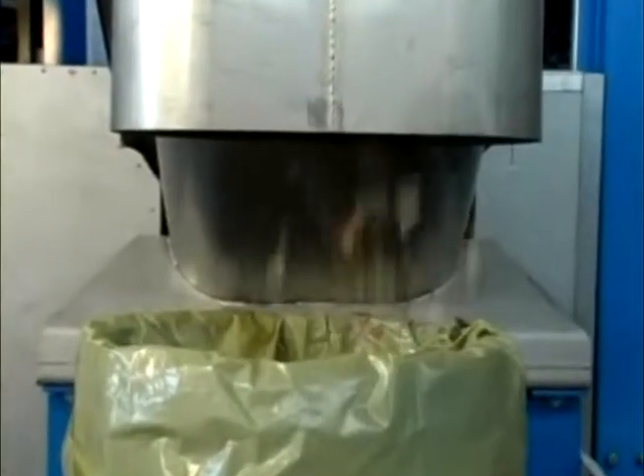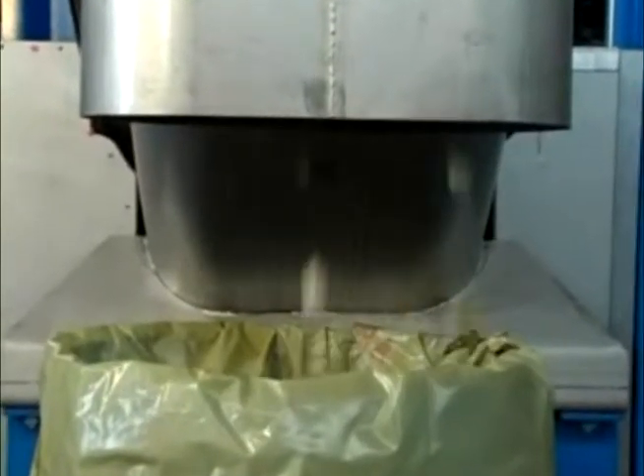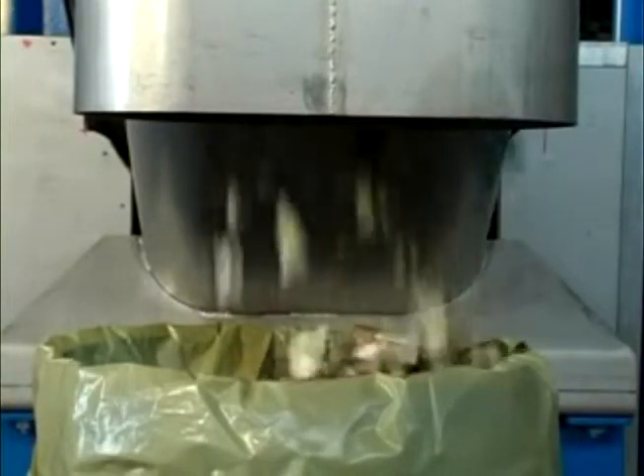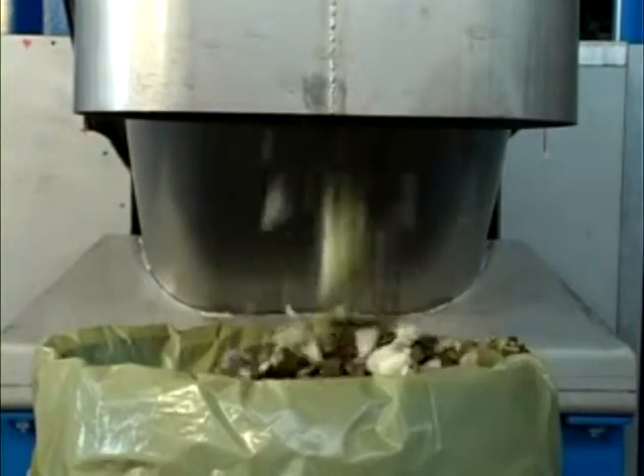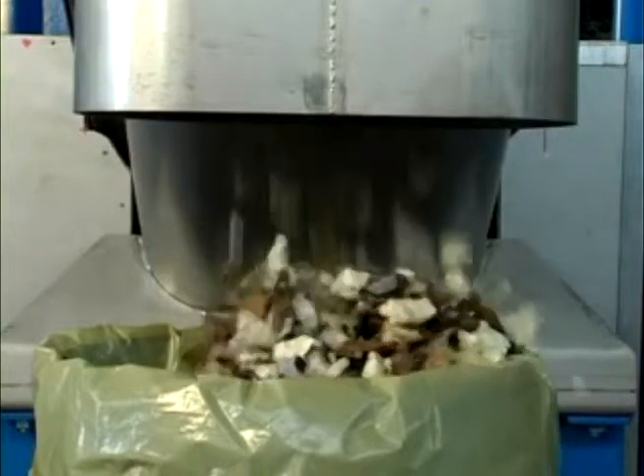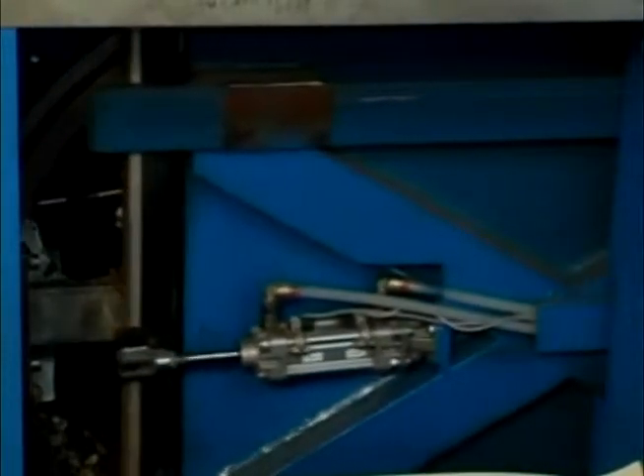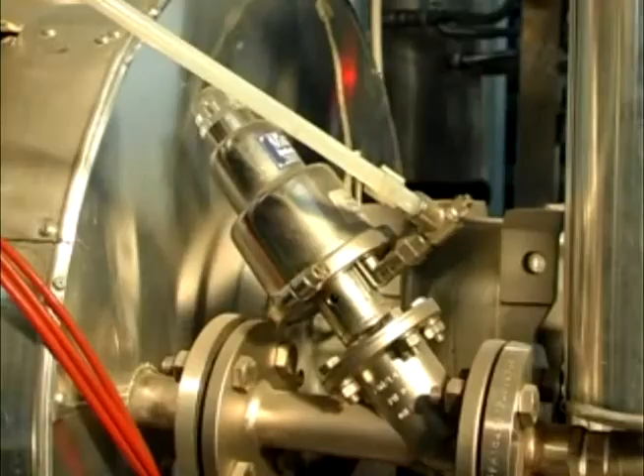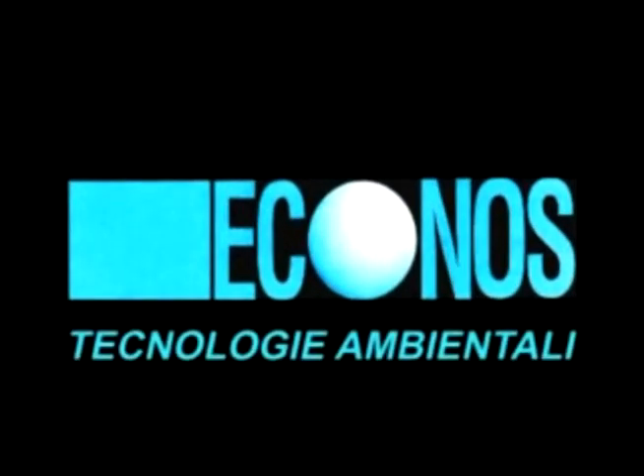as solid urban waste. After a set time, the unloading cochlea stops, and the automatic weighing system sends data to the PLC, which will transfer them to the printer. Before opening the sterilization chamber, it is necessary to come back to ambient pressure. The steam is discharged through a valve, which sends it to a condenser. Econos, tecnologie ambientali.